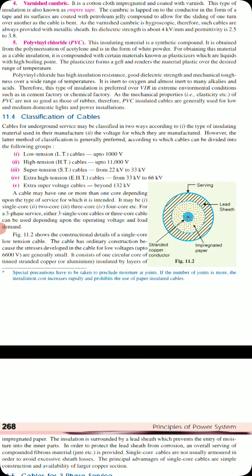A cable may have one or more than one core depending upon the type of service intended. It may be single core, 2 core, 3 core, 4 core, etc. For a 3-phase service, either 3 single core cables or one 3 core cable can be used depending upon the operating voltage and load demand. You can see in this figure the constructional details of a single core low tension cable.